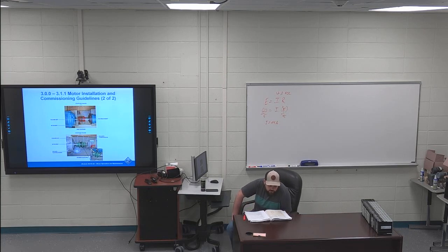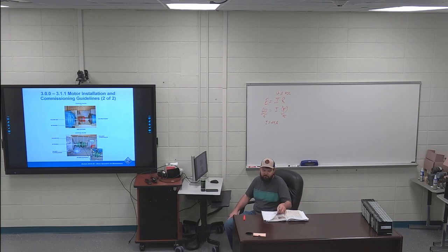The next bullet point is also highlighted: start the motor and ensure operation is smooth without excessive vibration or noise. If so, run the motor for 1 hour with no load connected. This is especially for larger motors. Whenever we would hook them up, we'd turn them on and let them run for a while, and this is like a wear-in period, getting stuff moving before actually connecting it to a load.